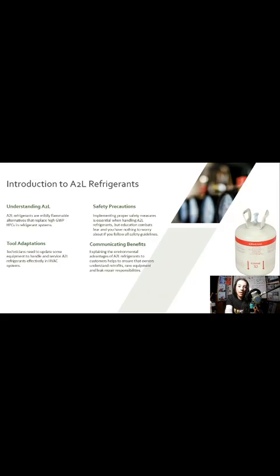Okay, so A2L refrigerants are mildly flammable, low GWP. GWP is different from the ozone depletion potential. Ozone depletion potential is that chlorine we're talking about. The 410As of the world don't have ozone depletion potential, but they do have high GWP, which is global warming potential. So though they're not destroying the ozone, they are heating the atmosphere, contributing to global warming. So what we want to do is drop that GWP, and make sure we're using low GWP refrigerants, which is our new A2Ls.